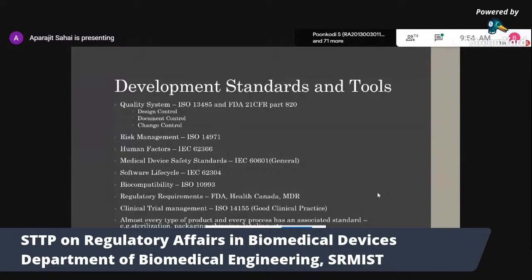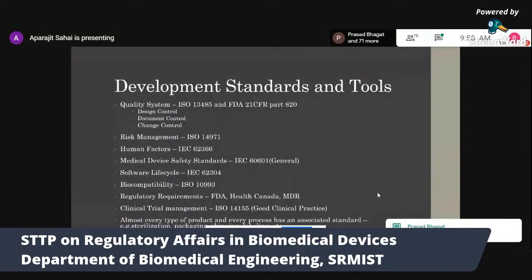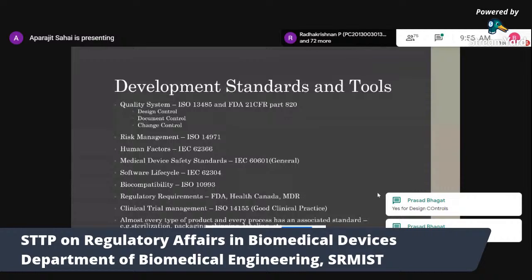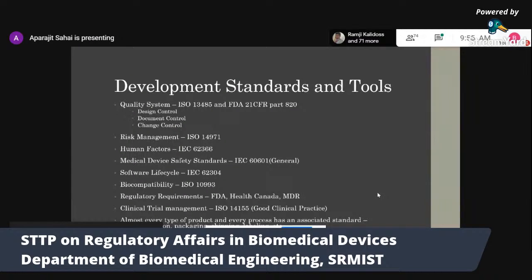If you're talking about quality systems, yes, that is also referred to as the QSR, the quality systems regulations. So yes, in terms of quality management and design controls, I am referring to FDA 21 CFR Part 820. And feel free to go and read those regulations. They've been written in such a way that anyone can understand them.